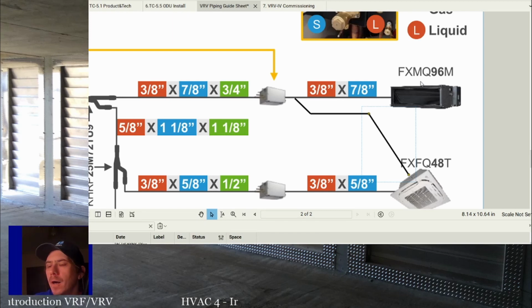A mistake I'll see engineers make sometimes when they design these systems, and it's not common, but it happens, is basically an oversight. I'll sometimes see a couple units that are in about the same area served off of a single branch selector, but one unit is on an outside wall and the other is, say, in the interior of the building.